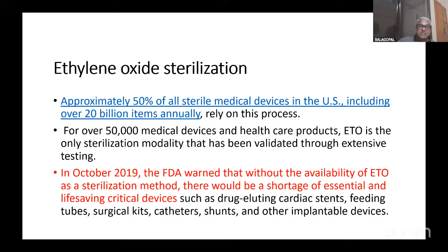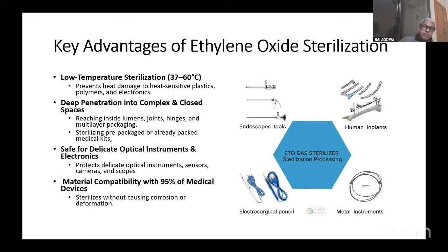So, the key advantages of ethylene oxide sterilization. It is still an important part of the sterilization tools that you have. One, it is a low temperature sterilization method, using 37 to 60 degrees centigrade, which prevents heat damage to heat sensitive plastics, polymers, and electronics. There is deep penetration into complex and closed spaces, particularly the scopes, reaching inside lumens, joints, hinges, and multi-layer packaging. Even when they are all pre-packed, they go into the ETO sterilizer pre-packed, and this is safe for delicate optical instruments like sensors, cameras, and scopes. And there is material compatibility with approximately 95% of medical devices without causing corrosion or deformation.